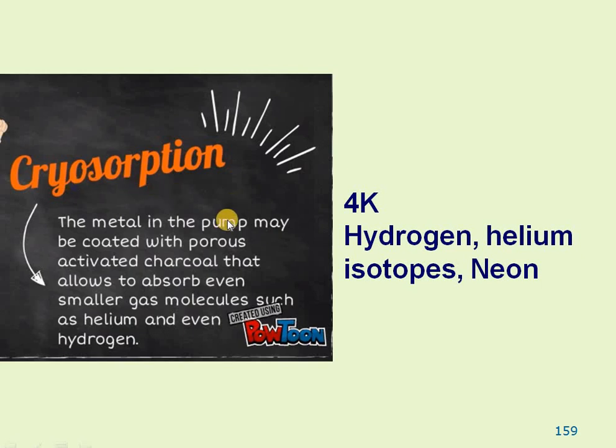Finally, cryosorption handles remaining molecules like neon, helium, and helium isotopes (He-3, He-4). Inside the pump, surfaces are coated with activated charcoal or zeolite materials at very low temperatures of around 4 Kelvin. These materials have high affinity to catch and hold helium-like molecules. Some hydrogen molecules are deposited by entrainment; the remaining hydrogen molecules are also deposited in the cryosorption stage.